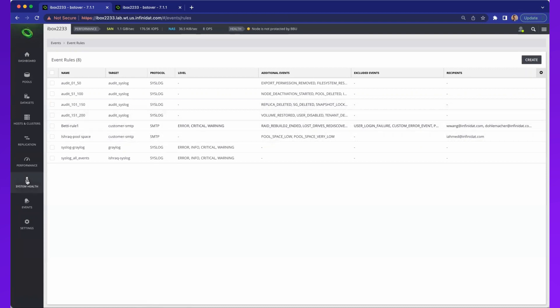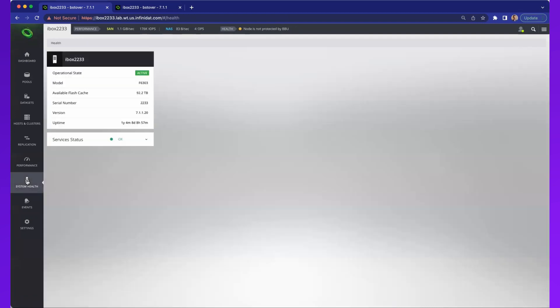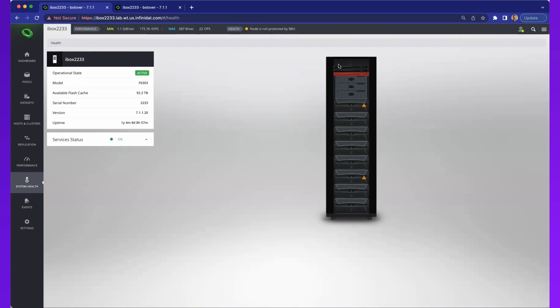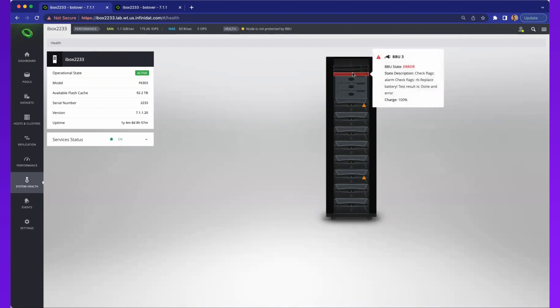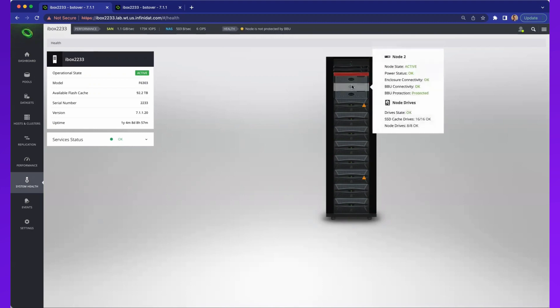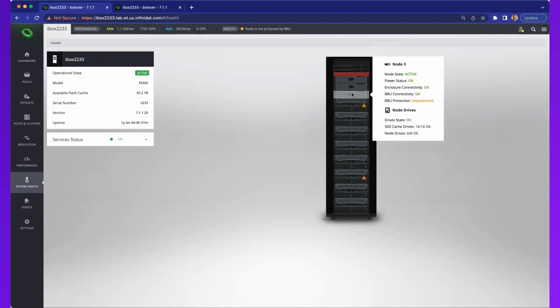If we come over to system health, this is what we saw at the beginning. We noticed that node had a BBU error. If we mouse over any of these elements at the top, I can see that there's a BBU that has an error state. If I finish going down over the nodes, this is telling me the node that's impacted, that it doesn't have the BBU protection. So it has one leg of power that's raw feed, and another leg of power coming from the BBU.